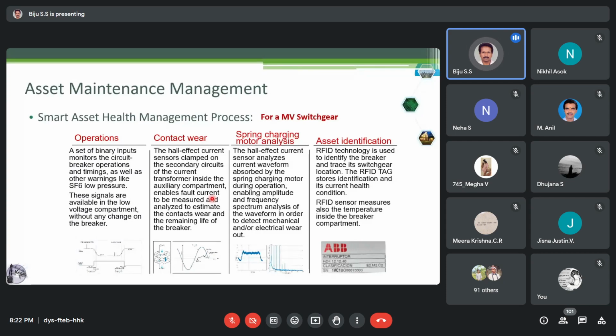So you have to monitor the condition of the contacts, which will give you an indication of the remaining life of the breaker. Through Hall effect current sensors clamped on the circuits of the current transformer, the fault current is measured, and by modeling the breaker, you will see how much the contact has deteriorated or worn out. Again, the spring charging motor current will be monitored to see whether there is any mechanical deterioration in the system. If there is mechanical deterioration, the spring charging motor will take more time and more current to charge the breaker. Again, the asset will be identified through RFID technologies, or there can be a QR code. Those things can be used for identifying the asset, and that information is fed to the system.